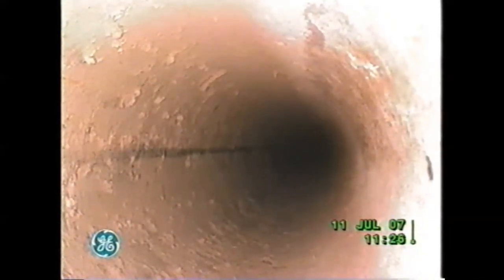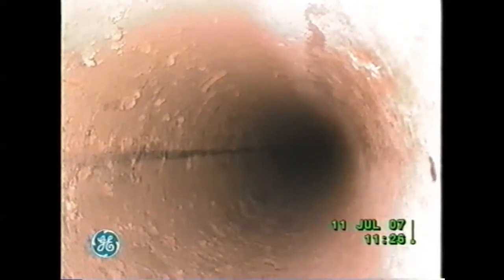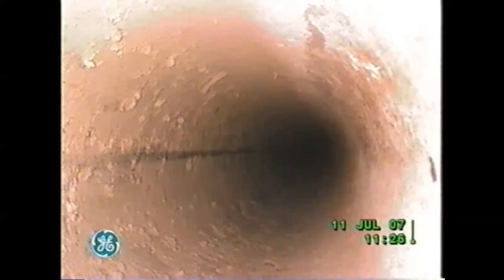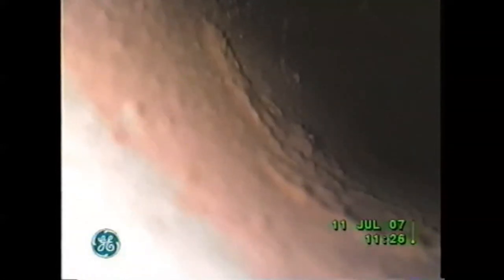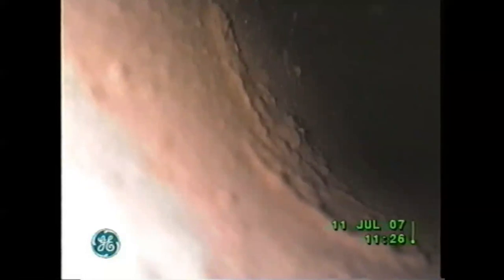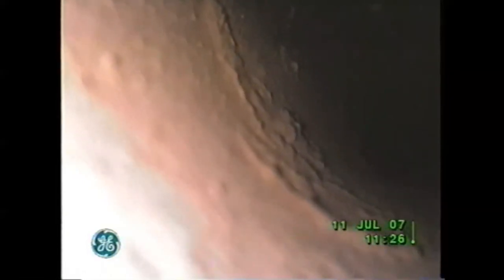So the story the company tells is that they fired a guy 3 or 4 years before I got there, and he managed the boiler house, and he didn't do a very good job on water treatment. He probably ran things for 5 to 7 years. And this is what happens when you ignore your water chemistry for 5 to 7 years. Look at all that crap.